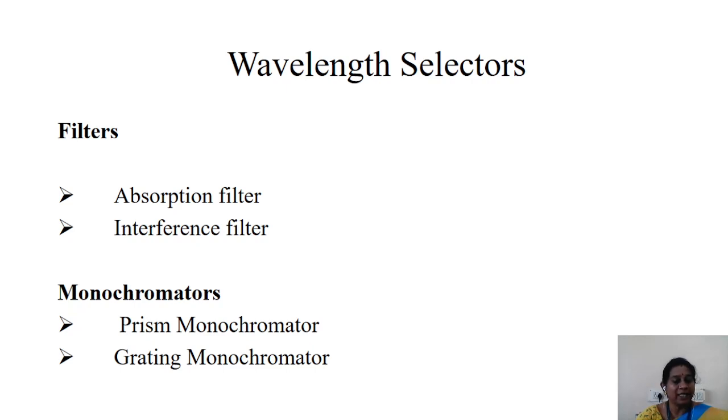The two main requirements of a filter are it should have high transmittance at the desired wavelength and it should have low transmittance at other wavelengths. The types of filters are absorption filter and interference filter. In this lecture session we'll discuss about the construction of these filters and their working.